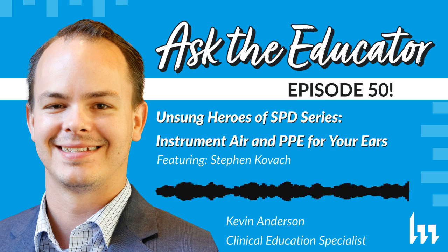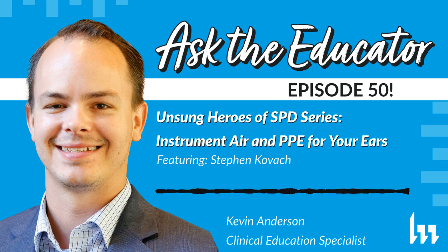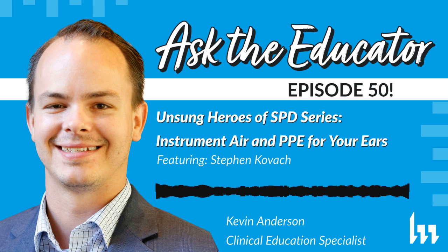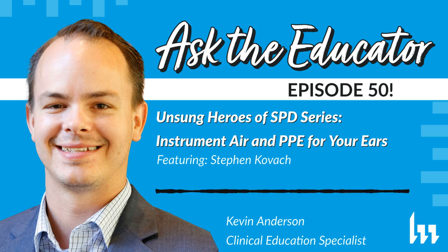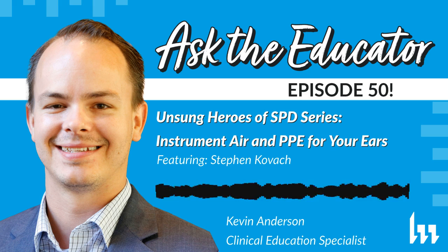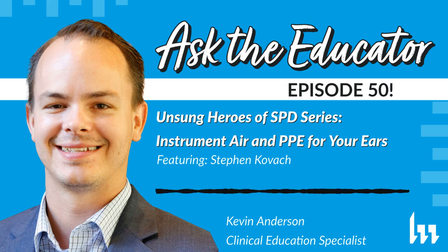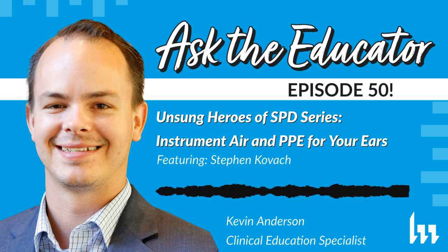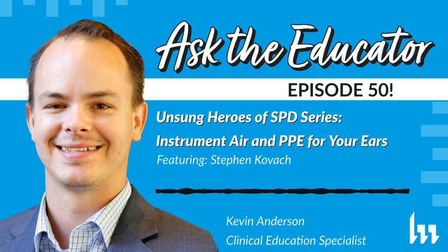So within that, the industry now has all these different air dryers, and companies have come up with ways to blow air through the scopes to get them dry and so on. And in some of the IFUs, you will find that you can only put in pressure up to a certain amount. So I see people who bring air in, but they don't have a way of monitoring the pressure. You've got to make sure you have a gauge or something that you can set to the maximum air that comes out.